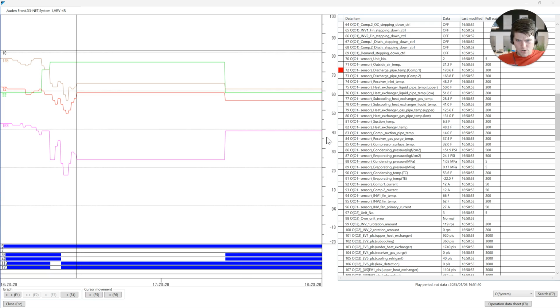Let's move on. As we're moving on here, we're going to get down to the end of this. Again, I don't like to troubleshoot in special control modes. Now, they teach you this in class. Can you? Of course you can. However, when we think about special control modes, there's so much gray area there that Japan has not shared with us. Even internal people, which I'm not internal anymore, but when I was, there's a lot of information that we don't know. Because of that, if we're going to start troubleshooting in special control modes, you have to have a firm grasp of what that control logic is and how it operates. Otherwise, you're making a lot of assumptions, and everybody knows what happens when you assume something, right? And so let's move on and let's get out of defrost.